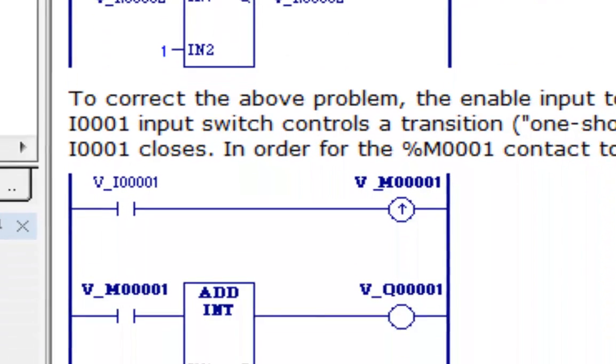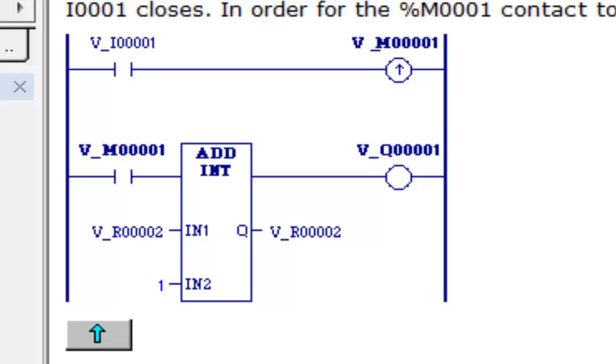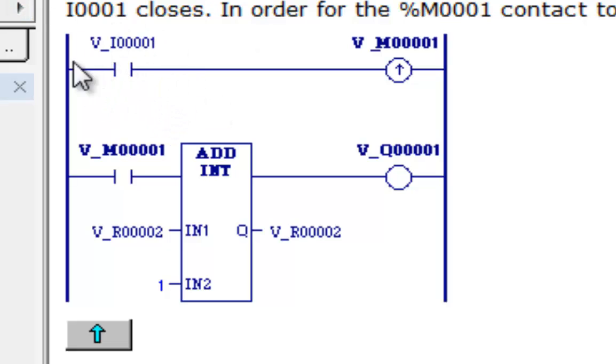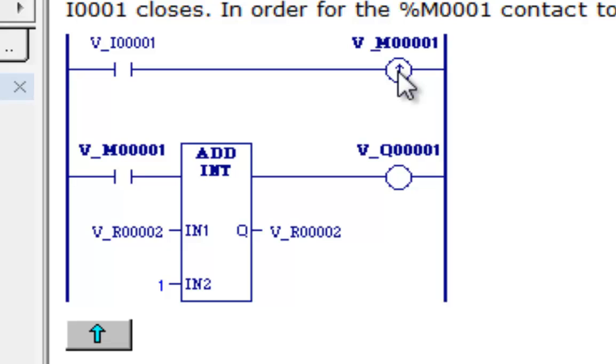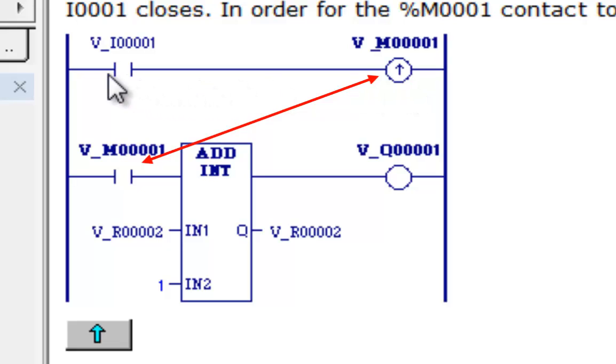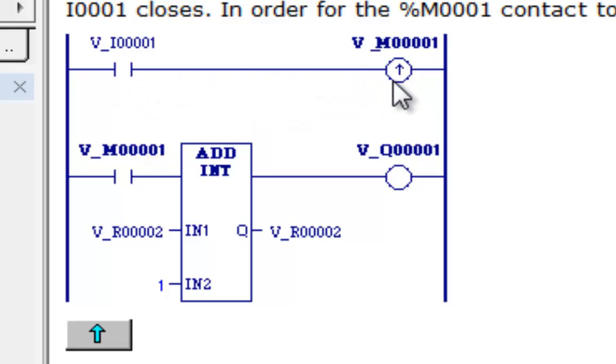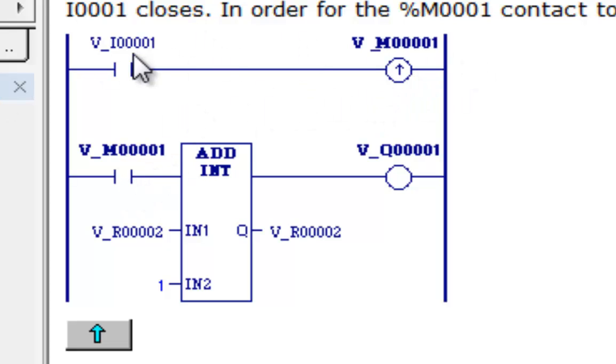But what the help file shows you is to correct that, you route your input here into a one-shot coil. And it will only be enabled for one scan. So in order to re-enable it, the contact has to open up and then close again. And once you have this setup right here, you'll use the M1 input into your add function, and you will only get one input for every transition.